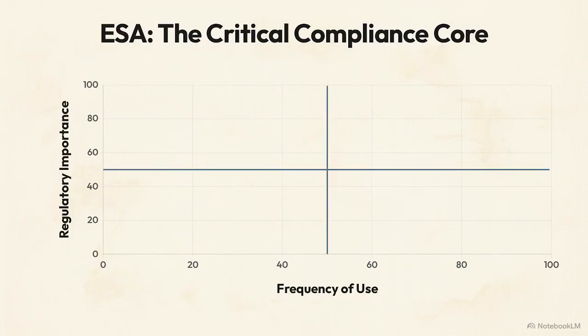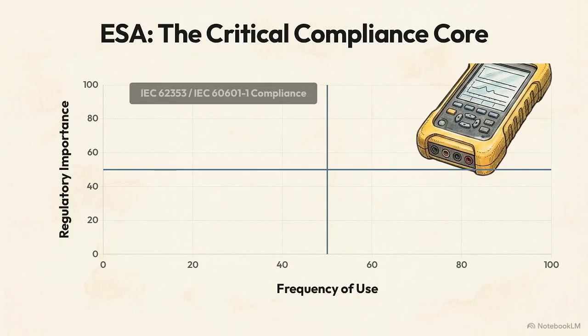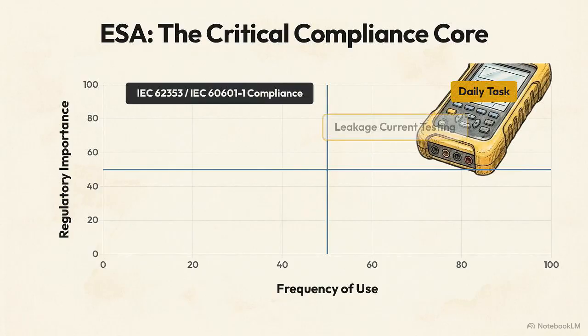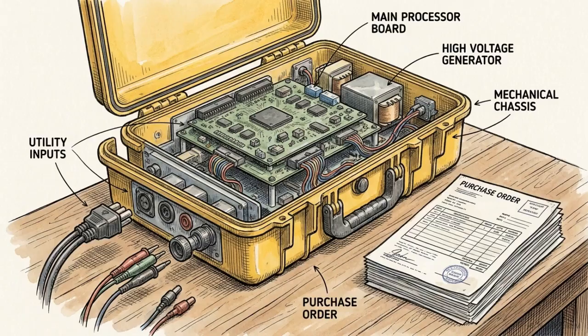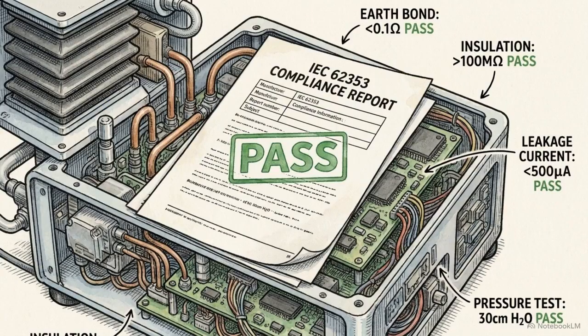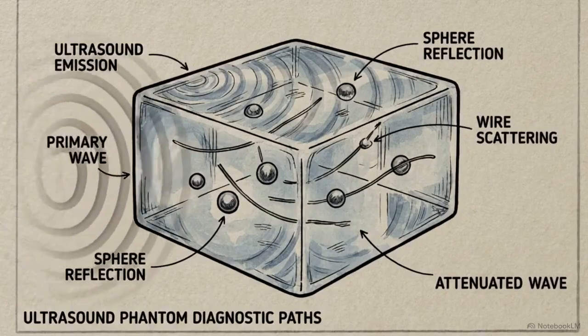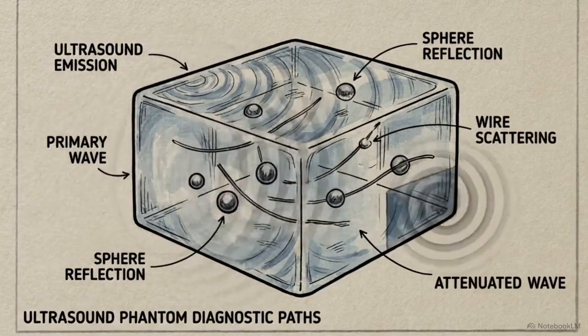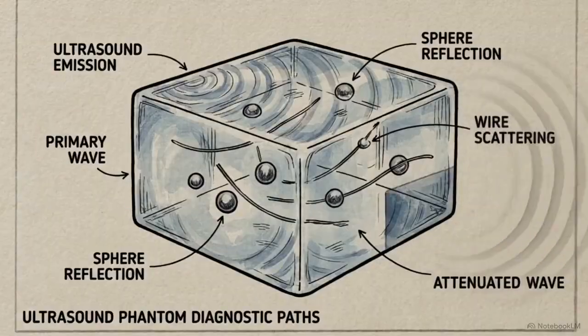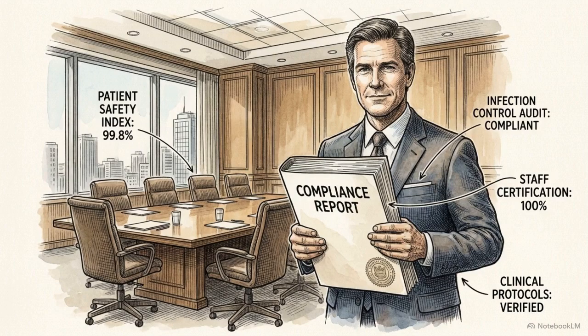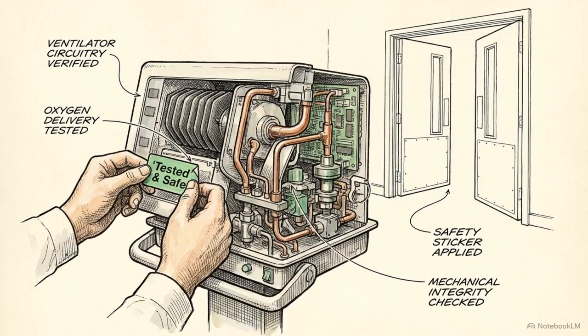This quadrant chart plots out biomedical analyzers, the most expensive and critical category of tools in the facility. Electrical safety analyzers sit in the top right quadrant. They are used daily to measure leakage currents and ground continuity. ESAs represent a massive capital expenditure for a tool that doesn't actually perform a repair. However, they are mandatory to verify compliance with IEC 62353 standards and protect patients from electric shock. You will also rely on specialized vital sign simulators and ultrasound phantoms to verify diagnostic outputs and therapeutic functions without using a human subject. These analyzers serve as the legal shield of the hospital. They provide the final, documented proof that a machine is clinically safe before it returns to a patient's room.